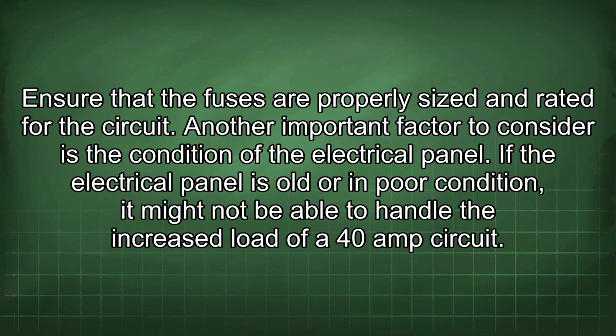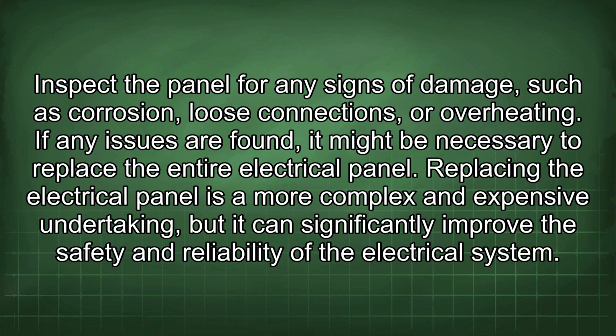Another important factor to consider is the condition of the electrical panel. If the electrical panel is old or in poor condition, it might not be able to handle the increased load of a 40 amp circuit. Inspect the panel for any signs of damage, such as corrosion, loose connections, or overheating. If any issues are found, it might be necessary to replace the entire electrical panel. Replacing the electrical panel is a more complex and expensive undertaking, but it can significantly improve the safety and reliability of the electrical system.